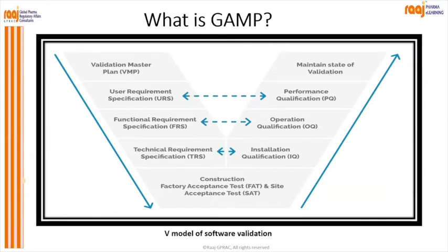If the machine is very huge, for example a compression machine, fluid bed dryer, or anything else, just think about an X-ray machine or the CT scanner in the case of medical devices. When you dismantle each and every part and transfer it by courier, by surface or air, and it is installed again at your site, there are chances of haywire results or some part being damaged during transport. So that is why FAT and SAT become very important.